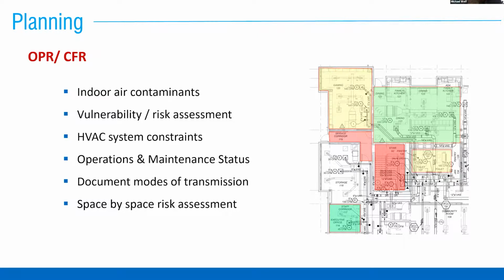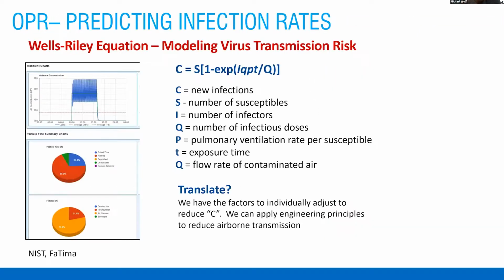So really we boiled that down into the client essentially saying, I want to focus on dilution and filtration. Again, tying directly back to that ASHRAE position document on infectious aerosols, and looking at how we measure that in the OPR, the dilution being 3 air change rates of outdoor air, and for the filtration, they wanted a MERV 13.